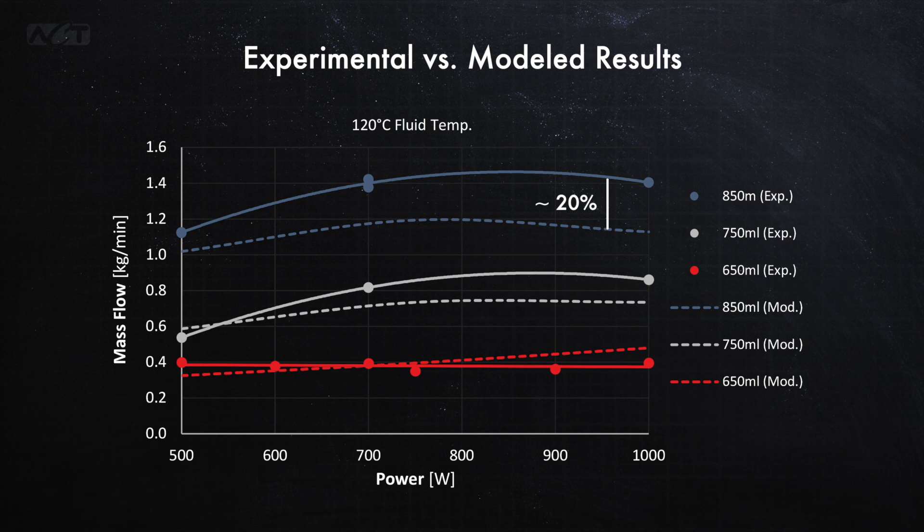While 20 percent is significant, it's well within the typical predicted ability of the two-phase frictional pressure drop correlations that we use. And importantly, the model was shown to be capable of predicting the trend of increasing mass flow rate with increasing charge. This initial work demonstrated that the model is capable of predicting the mass flow rate for a two-phase loop thermosyphon.